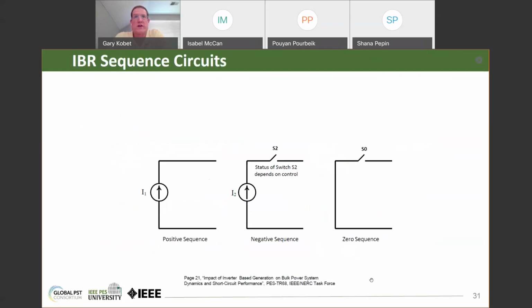this is a representation of an IBR in the 3 sequence networks. It's a constant current device in the positive sequence network, and no zero sequence current, so the switch is open on the far right. And then in the middle, whether you get negative sequence current or not is dependent on the control system programming. And so where conventional protection systems are depending on negative sequence current, there may not be significant negative sequence current for an unbalanced fault. Next slide, please.